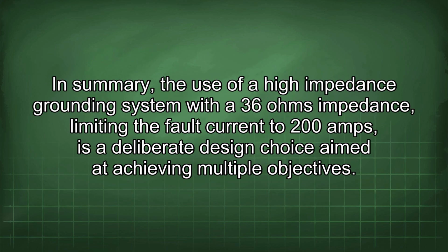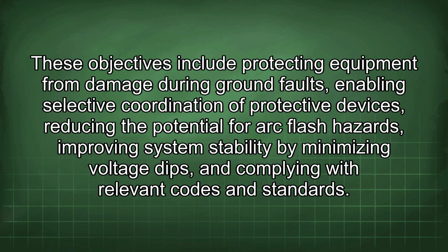In summary, the use of a high impedance grounding system with a 36 ohms impedance, limiting the fault current to 200 amps, is a deliberate design choice aimed at achieving multiple objectives. These objectives include protecting equipment from damage during ground faults, enabling selective coordination of protective devices, reducing the potential for arc flash hazards, improving system stability by minimizing voltage dips, and complying with relevant codes and standards.